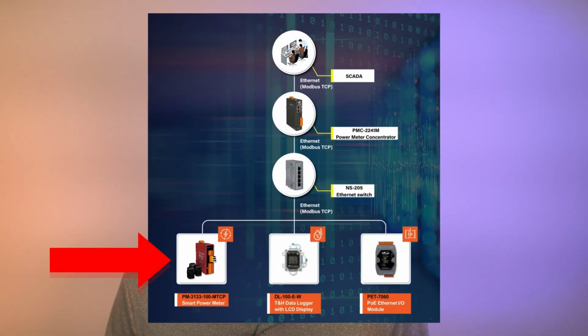Because as every data center operator knows, environmental control is only part of the story. To truly maintain reliability, you also need to understand what's happening electrically and how much power is being used and whether the quality of that power is stable. That's where the energy monitoring comes in. On the electrical side, we introduced PM3133 smart power meters to measure three-phase power at both the panel and circuit levels. These meters provide detailed insight into energy consumption, load balance, and power quality.